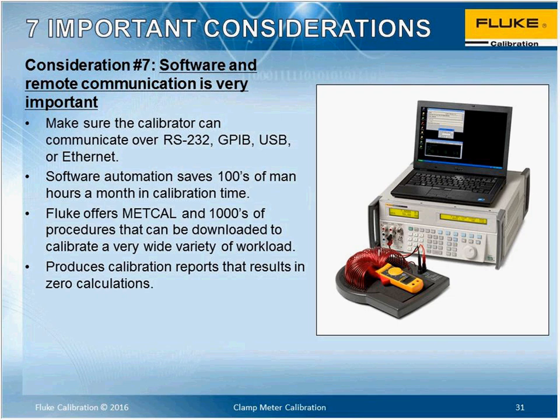So, for instance, if you were calibrating a handheld, maybe there's 5 to 10 calibration points, and that seems pretty extreme. But for the sake of this example, for every point you'd have to set the range, take the measurement, and write it down. With the calibration software, it basically runs through a script and sets the calibrator at its voltages, current, or whatever function it's performing, and it just asks you for the measurement. So you type in the measurement of the UUT, and it does all the calculations for you, and at the end you get a calibration certificate that tells you whether it is pass or fail.